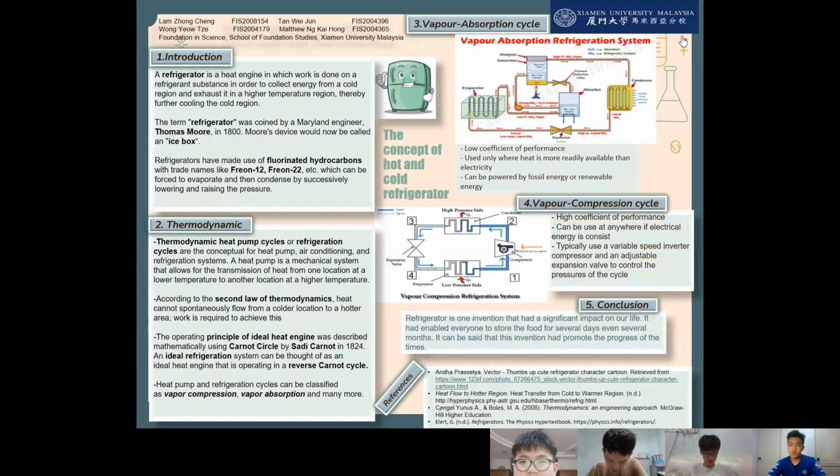At the start of the thermodynamic cycle, the refrigerant enters the compressor as a low pressure and low temperature vapor, where the pressure is increased and it leaves as a high temperature and high pressure superheated gas. This hot pressurized gas then passes through the condenser where it releases heat to the surrounding as it cools and condenses completely.